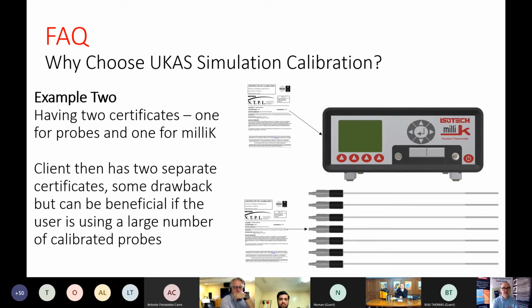where it can be a good idea to have two certificates. Here I've got one certificate for the milliK, and other certificates for the reference probes. Suppose the client has many calibrated probes, different manufacturers' probes calibrated at different times. If they've got several probes, it's not necessarily convenient to always have the probe and the milliK calibrated together. So it can be beneficial when you've got a lot of standard probes to have a calibration certificate for each probe, and then another calibration certificate for the milliK. There's some drawback, but it also can be beneficial when you've got a lot of probes.